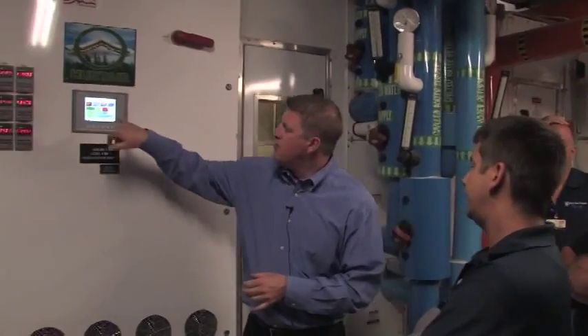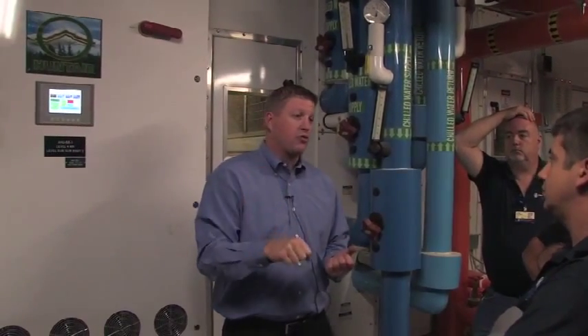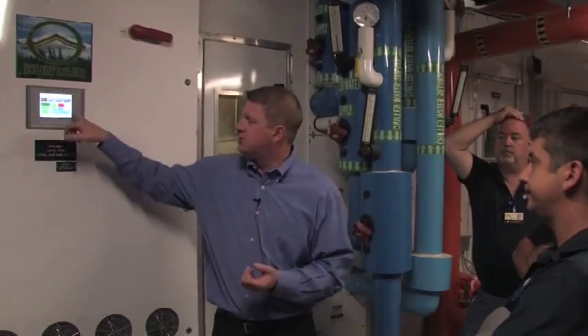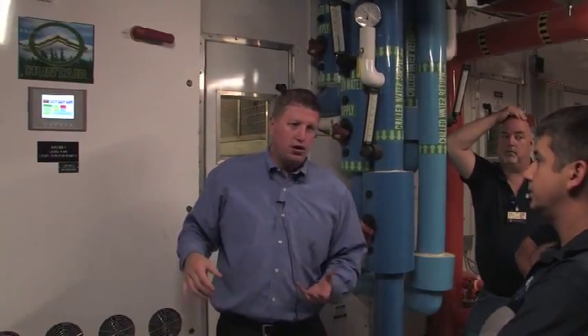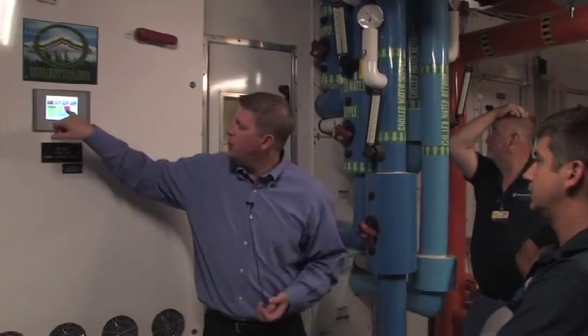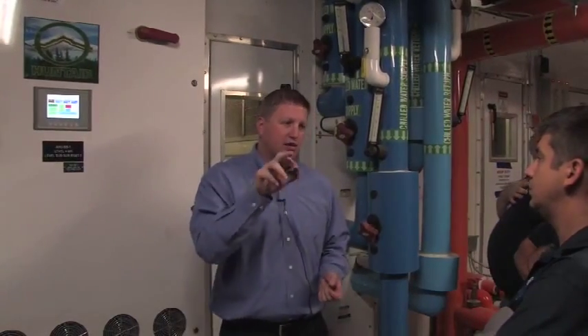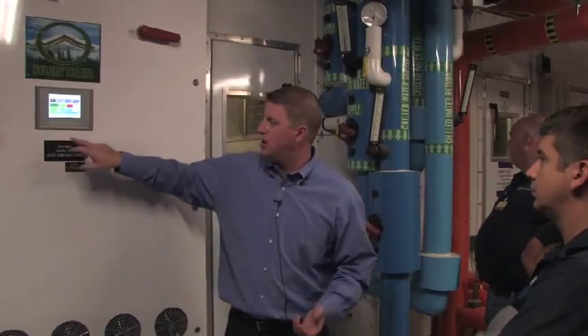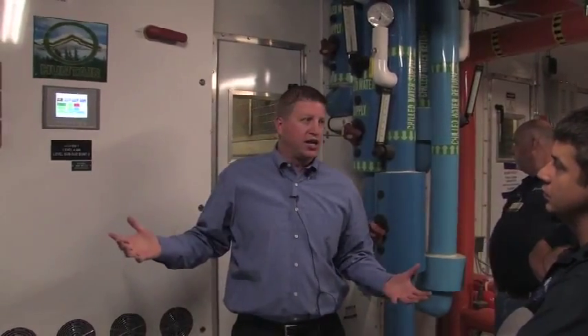What's the system and remote? System and remote. So that means right now E&E's controlling it. Your building management system is controlling this unit. Like on a VFD, you've got hand, off, auto, right? Hand means I'm controlling it. Auto means the BMS. So this is right now in auto. If I wanted to put it in hand, I would hit local control. And then I can, you know what, do you guys want to do it? Might as well. So if I want to control this thing in hand, I can hit local control.